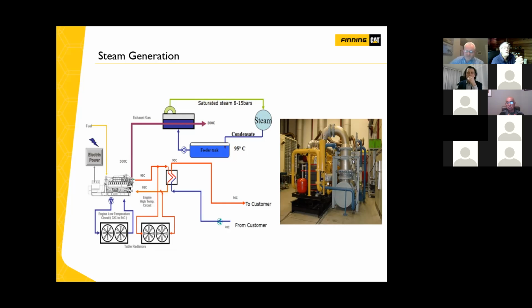A recip engine can only really generate low-grade steam because of the relatively low temperatures. And if you need high-grade steam, turbines are probably a better option. And in most cases, the case to go with a recip or a turbine really depends on what the customer needs. But if the bias is towards electrical, gensets are a lot more efficient than turbines beneath 20 megawatts. Something to consider.